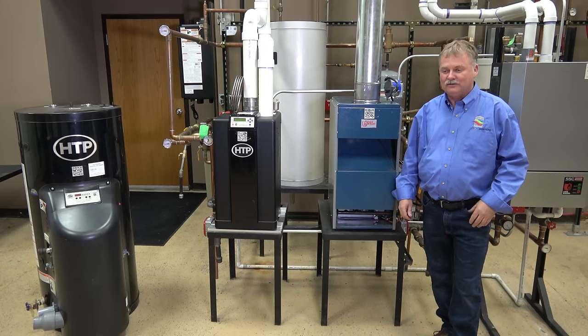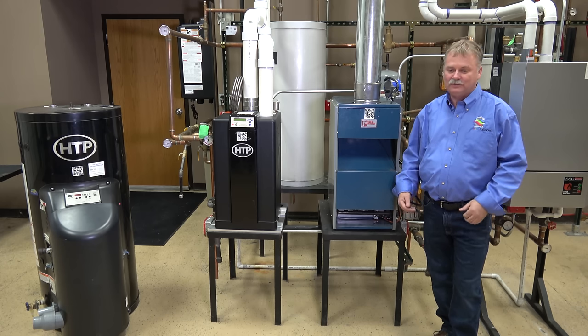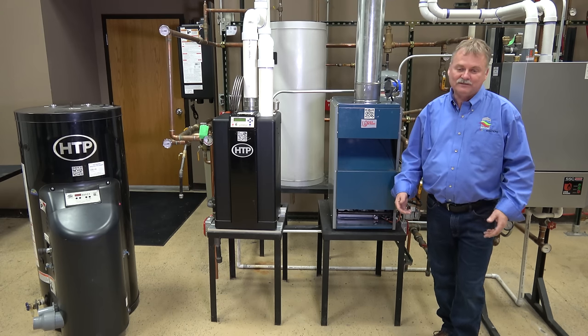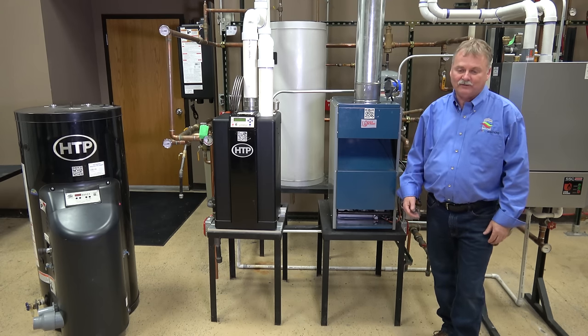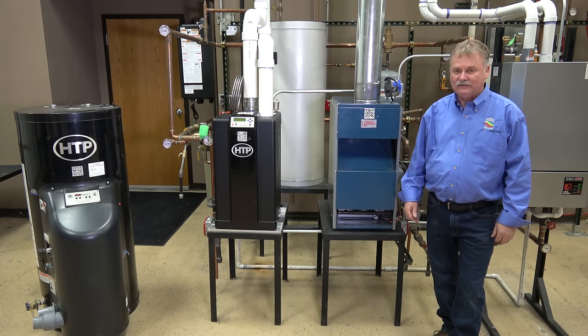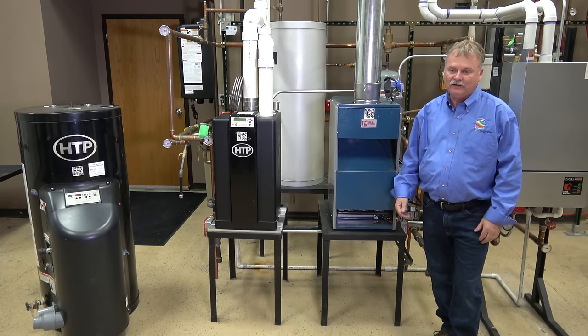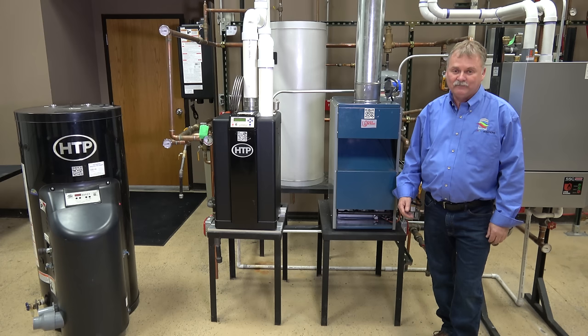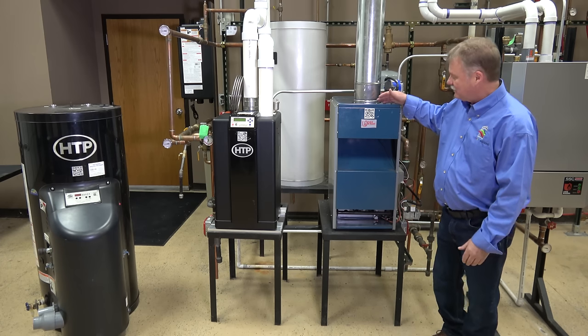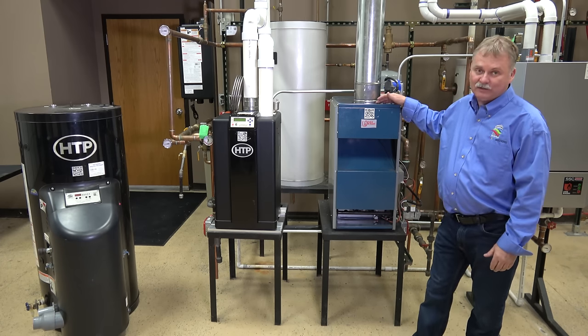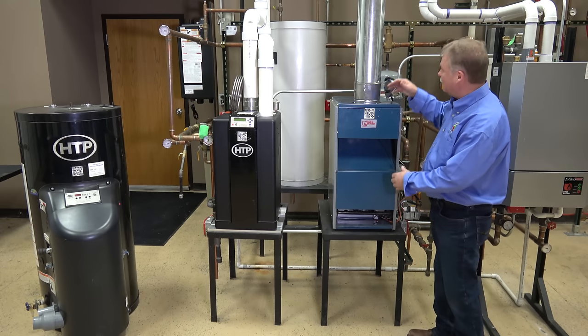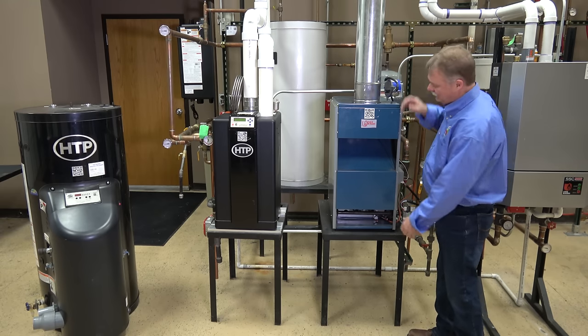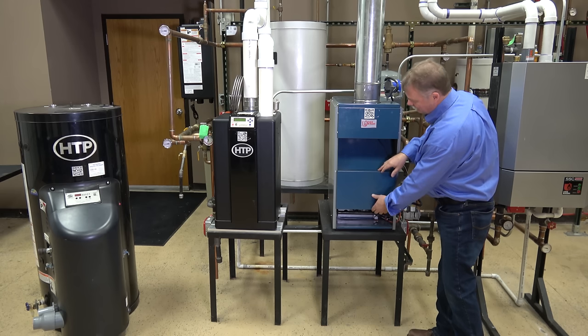Today what I want to talk about is just show you the differences between a typical cast iron boiler, which is basically the main boiler in the market right now, versus some of the new high efficiency boilers that have been around for a while, but are still new to a lot of people. First thing here is basically a standard cast iron boiler. What you have here is a standard flue. It normally goes into a chimney.